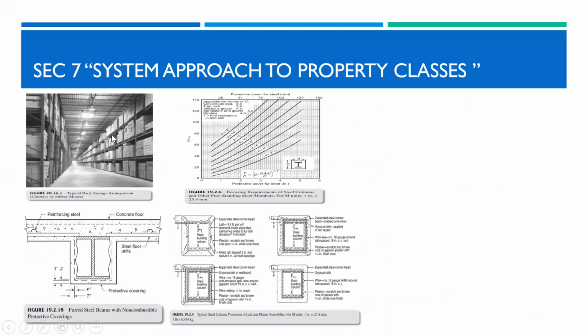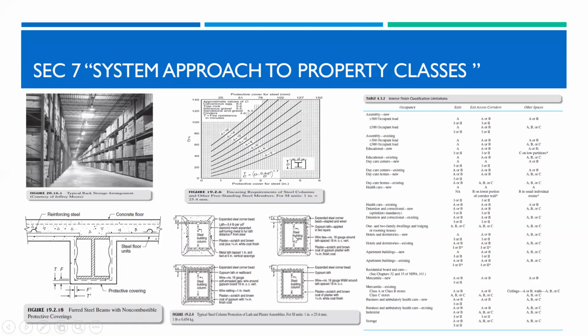As we see here, warehouse, how we can protect warehouses based on the ceiling or roof heights, storage heights, and type of storage. Here we have the building structures like steel beams, and how we can cover them with concrete in order to give the fire rating for the elements based on this curve. And we determine the depth of the cover based on the type of column, steel column. And from this table, we know the occupancy in order to determine the interior finish for ceiling, floor or wall, class A, B, C, based on the area, exit access or others.